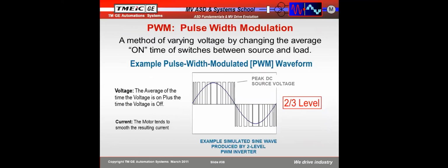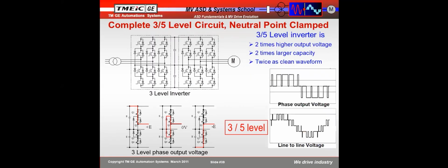Now, I'm going to call this a 2/3 level drive. Power system engineers would call that a 2-level drive. It's a 2-level drive because it has 2 levels between 0 and peak. So from 0 to peak, it's 2 levels. From peak to peak, there's 1 level, 2 levels, and 3 levels. It has 3-level drives. So I'm going to call this 2-level drive a 2/3, and that is the way all low voltage drives are created.